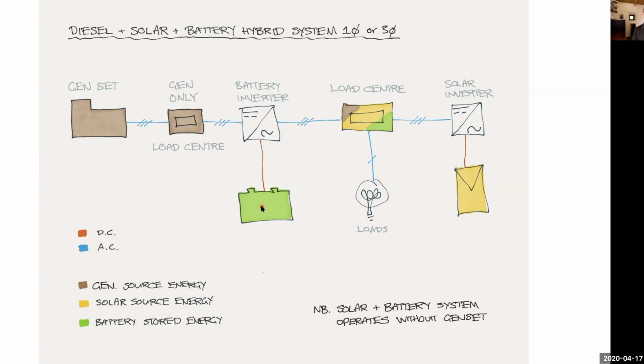You can add multiple solar inverters. They don't have to be one. You could actually have more than one, as long as there is some communication system that allows them to be controlled. So just to point out why a control system is required: if you've not got a grid connection, so this is off-grid, there's nowhere for surplus energy from the solar to go. It can't spill anywhere. So you really need to consider how you curtail, which is to reduce the output of that solar inverter, when the batteries are full and the loads are light and you just don't need the energy.